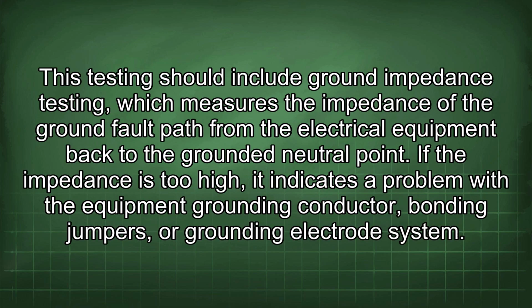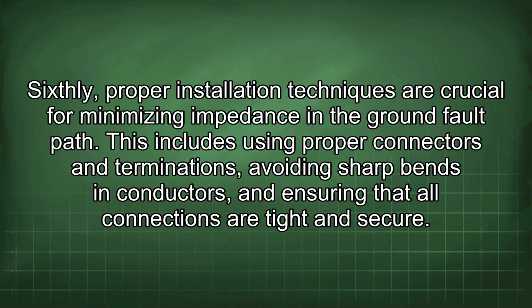This testing should include ground impedance testing, which measures the impedance of the ground fault path from the electrical equipment back to the grounded neutral point. If the impedance is too high, it indicates a problem with the equipment grounding conductor, bonding jumpers, or grounding electrode system. Sixthly, proper installation techniques are crucial for minimizing impedance in the ground fault path.